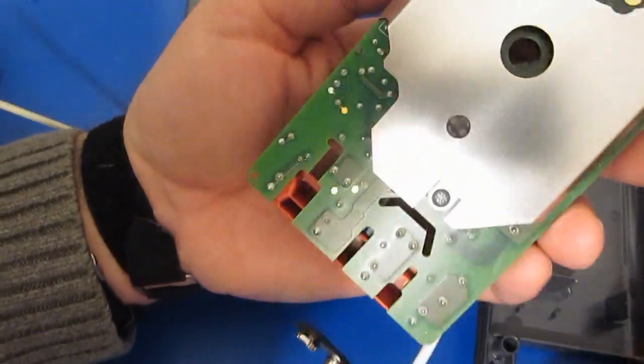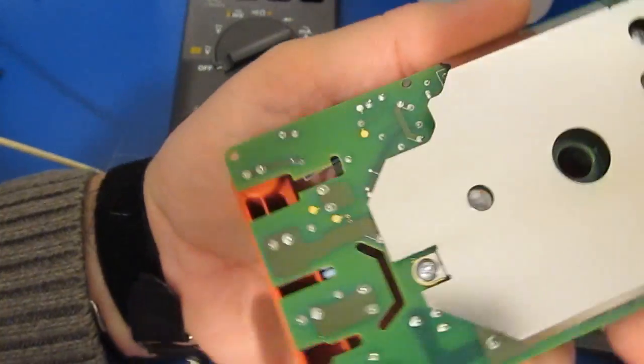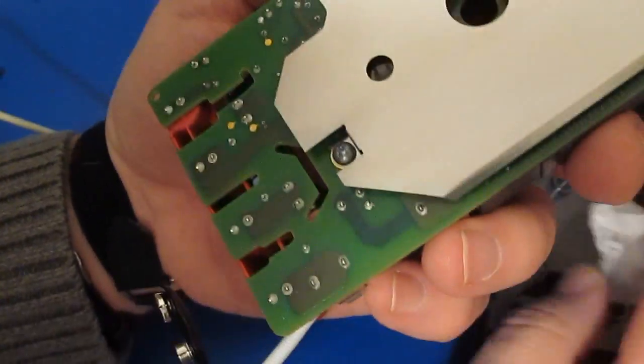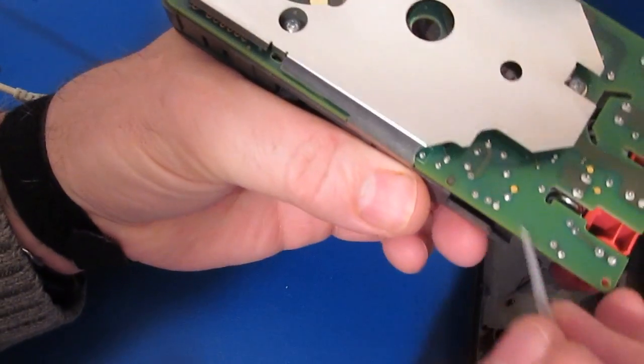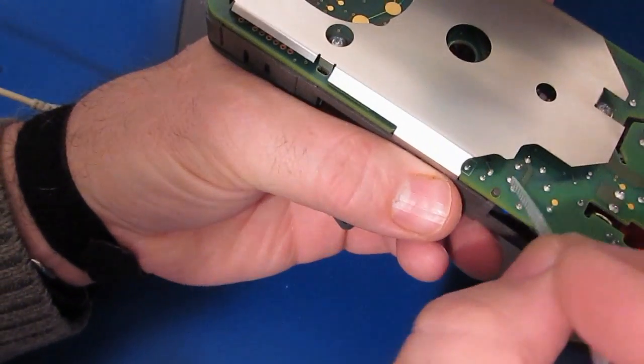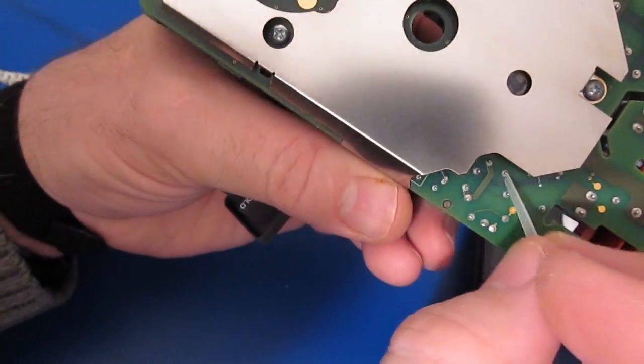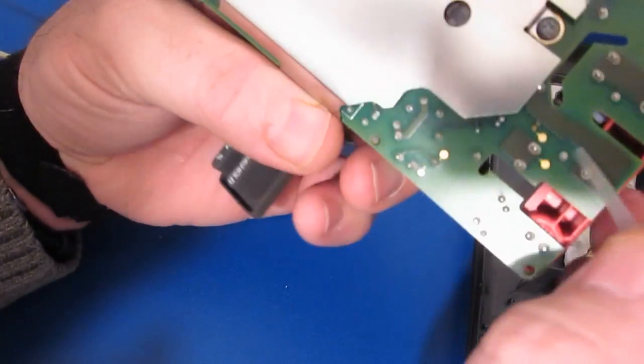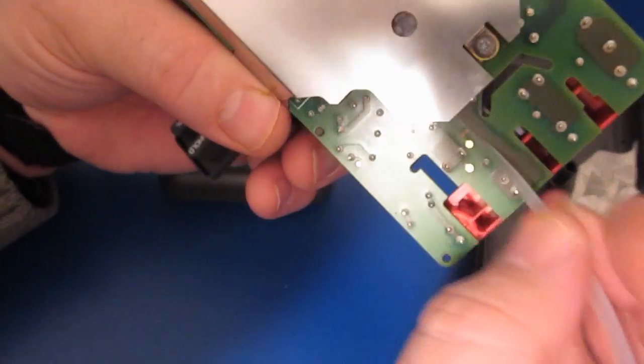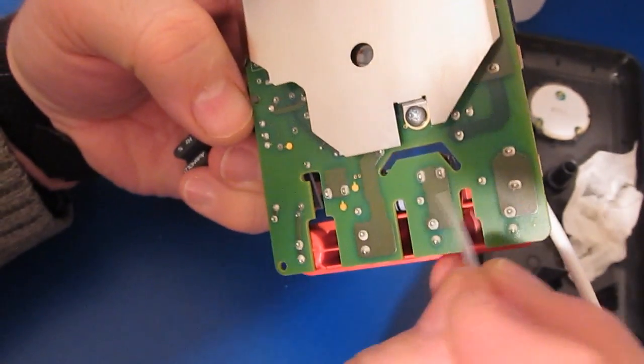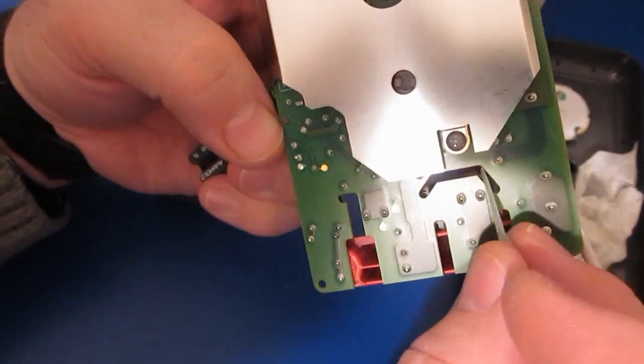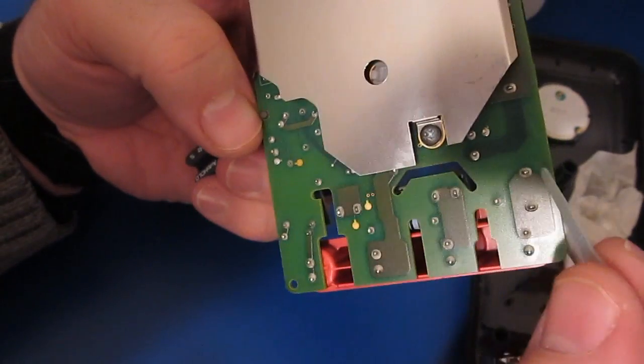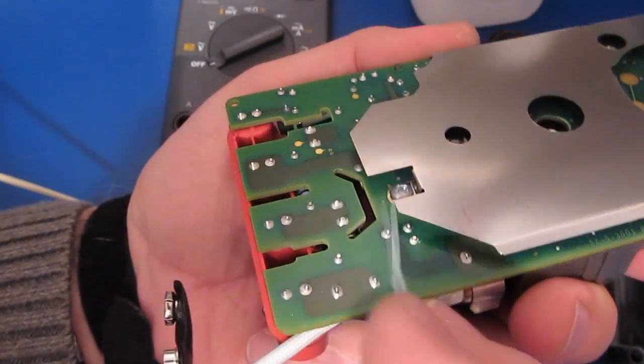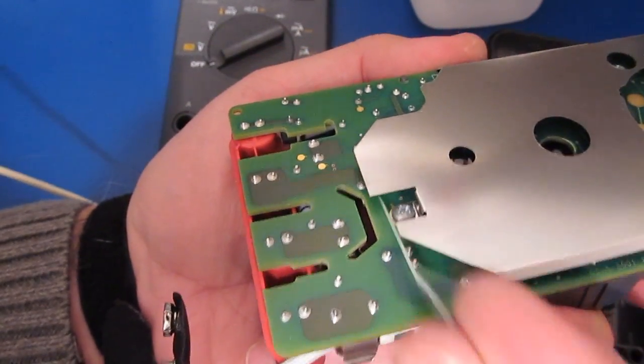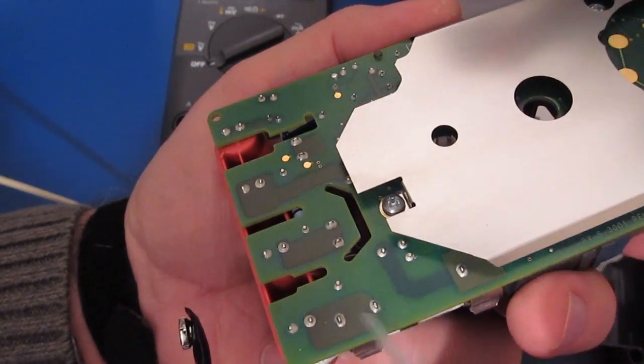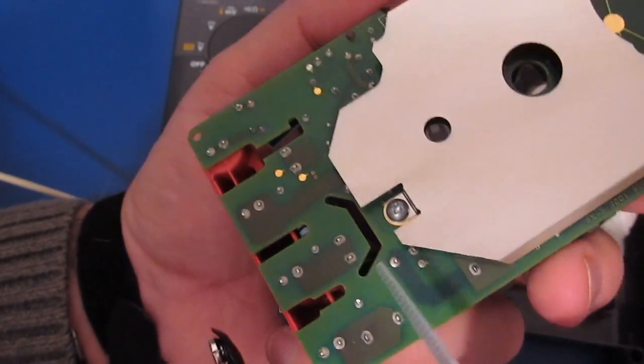One of the concerns was how close the shield is to the high voltage areas. All the high voltage is basically going to be in this area. The MOVs are right here, and you can see the shield's got a fair amount of cutout. This area here is the common point. We do have the fuse and the shunt, but you can see I've got this pretty good slit sitting across them, and the shunt going back to the common point is sitting across here. So I don't see it ever arcing from here up to the shield, that's not going to happen.